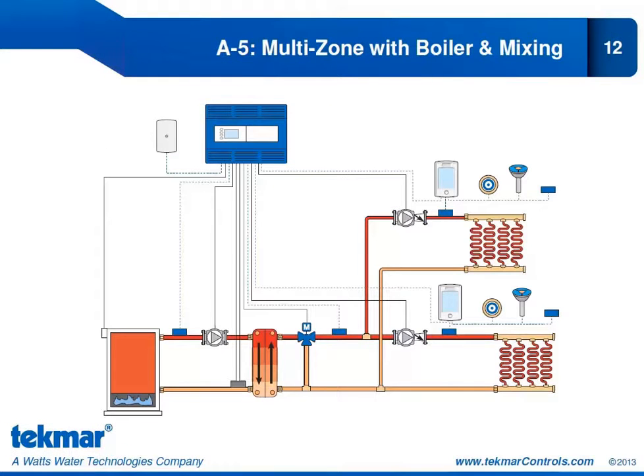Here's our fifth application, which is a multi-zone application where we're operating a boiler and doing some mixing to the snowmelt zones. We have 2 snowmelt zones in this case. Each one is being controlled by its own 654. We're showing you the 3 sensor options, the use of the 090 or 094, the snow sensor 095, and the slab sensor 072 or 073. You can see we are connected to a TN4 system. We have a reset module on the left-hand side and a zone manager on the right-hand side.